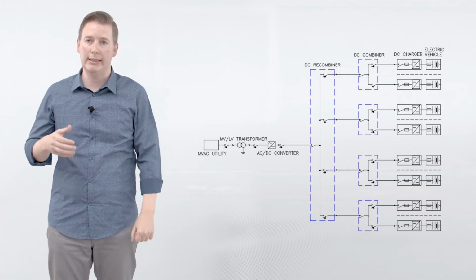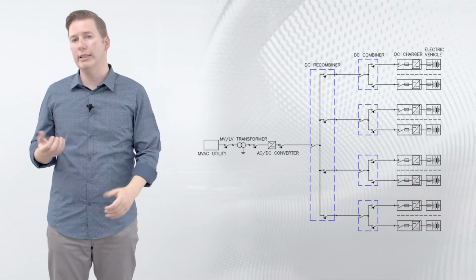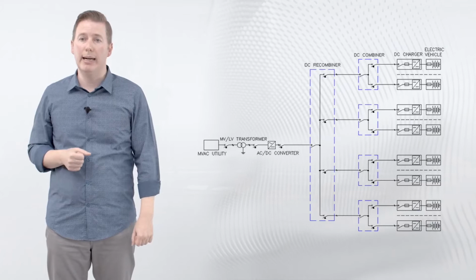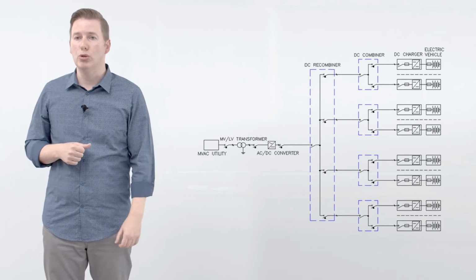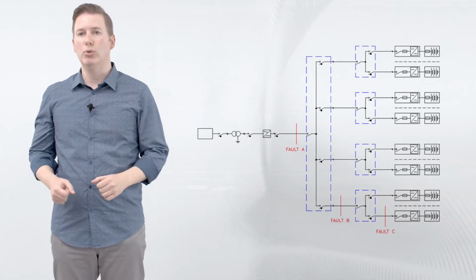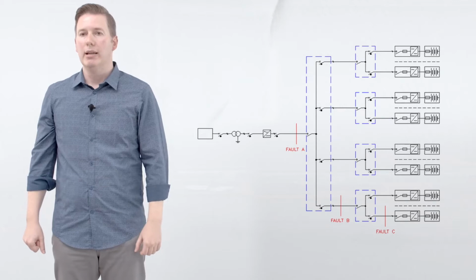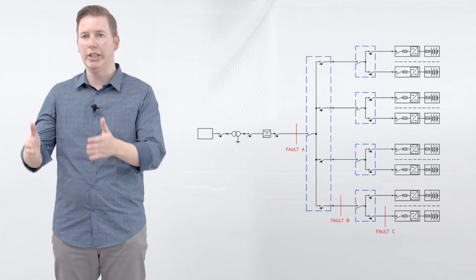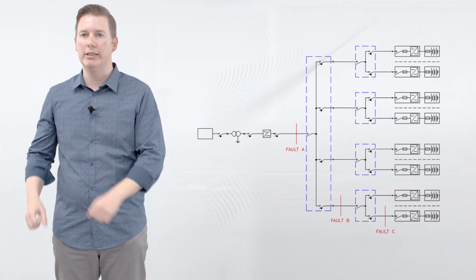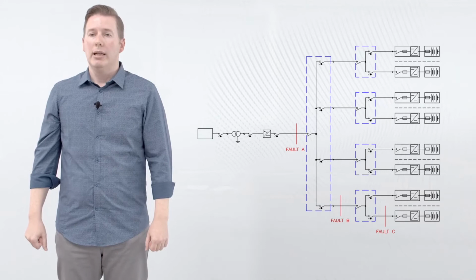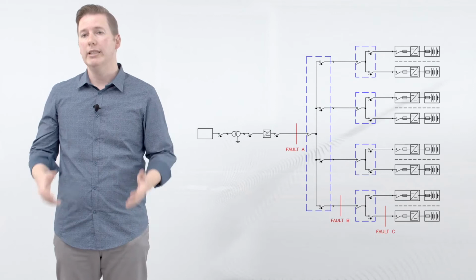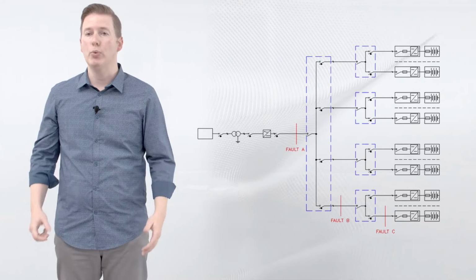Immediately at the DC output of the converter, we have a circuit breaker, usually, to protect the DC bus and, according to its internal architecture, to protect the AC-DC converter itself, as we can see later on. Considering the short circuit event, the several fault locations where a short circuit can occur are here represented. Fault A, between the main AC-DC converter and the DC recombiner. The fault B, between the DC recombiner and each DC combiner, and fault C between each DC charger and the relevant DC combiner. Each fault has several current contributions, and each circuit breaker will detect the total short circuit current, which can change according to the fault location.